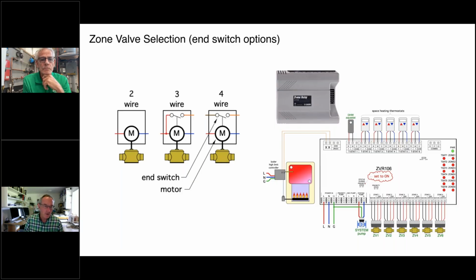Certainly, if it's a 3-wire zone valve, you can replace it with a 3-wire. I like 4-wire because now you have an isolated end switch. That end switch can go to a completely separate circuit operated by a separate transformer. You don't have to deal with a single transformer. If you simply don't need end switches, you can order a 2-wire zone valve.